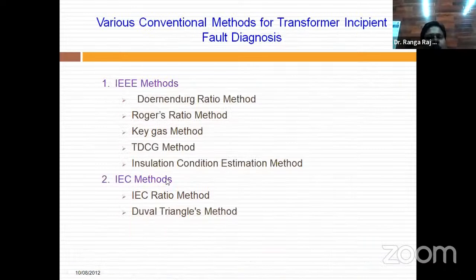Here I've discussed one. There are different methods, IEEE methods and IEC methods. Through these methods, we can determine the fault. These methods are detailed based on the gas concentrations, whatever we get from the DGA test. Researchers across the world developed these basic methods and they've become very standard these days. Even in the field, field engineers follow these methods to determine the fault. But each and every method has some problem, some drawbacks.